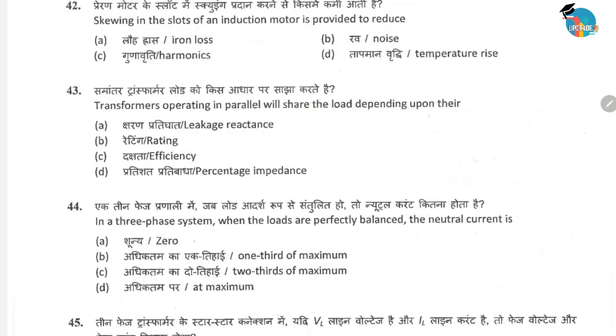Next question is, transformers operating in parallel will share the load depending upon their? Options: leakage reactance, no, it is not correct. Upon the rating, no. Upon the efficiency, no. The correct option is option D, that is the percentage impedance. Transformers operating in parallel will share the load depending upon their per unit impedance, that is, the percentage impedance.